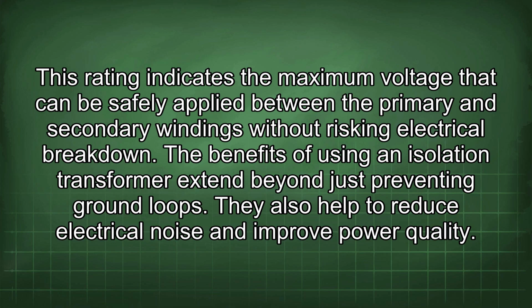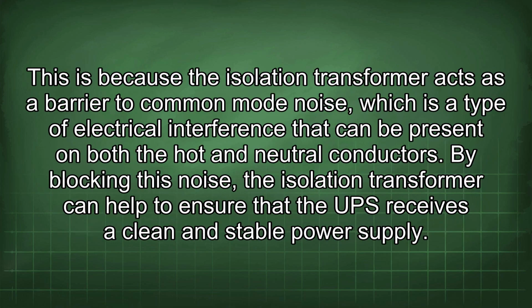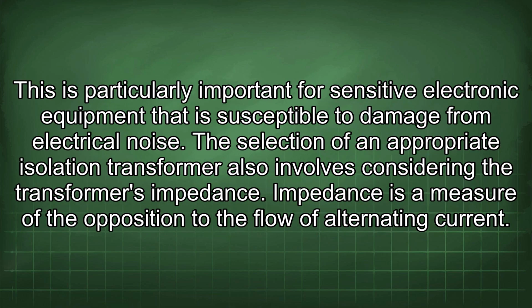The benefits of using an isolation transformer extend beyond just preventing ground loops. They also help to reduce electrical noise and improve power quality. This is because the isolation transformer acts as a barrier to common mode noise, which is a type of electrical interference that can be present on both the hot and neutral conductors. By blocking this noise, the isolation transformer can help to ensure that the UPS receives a clean and stable power supply. This is particularly important for sensitive electronic equipment that is susceptible to damage from electrical noise.